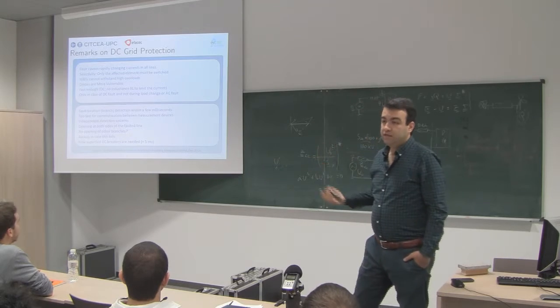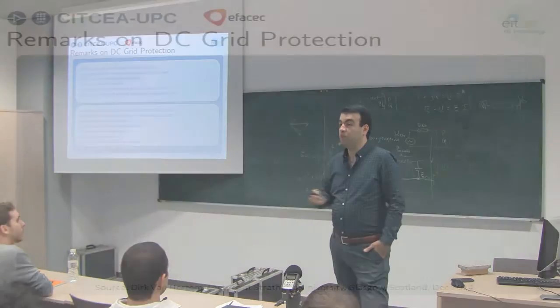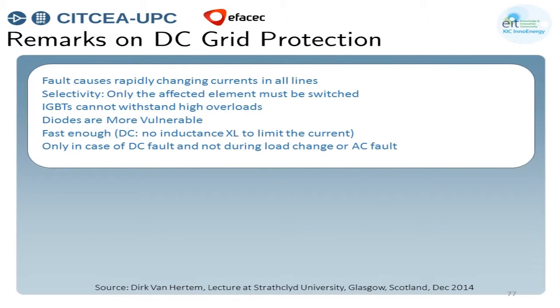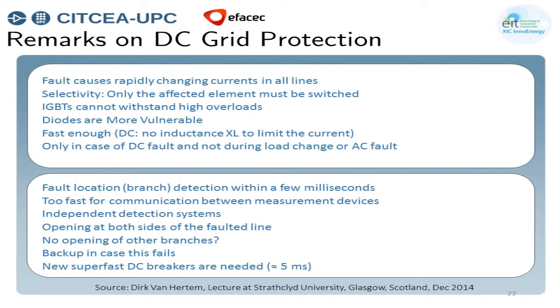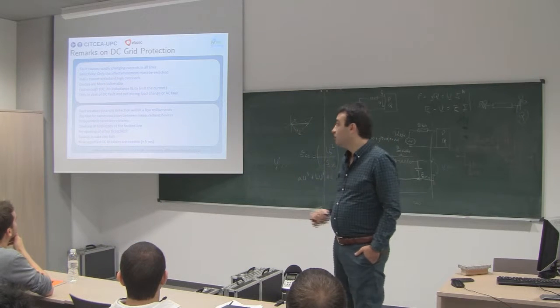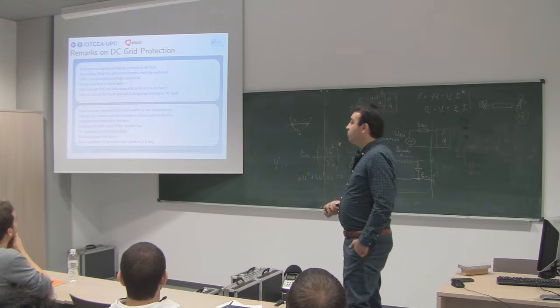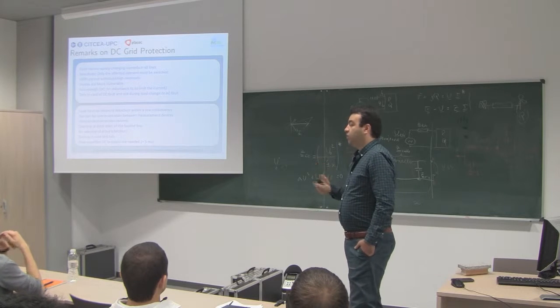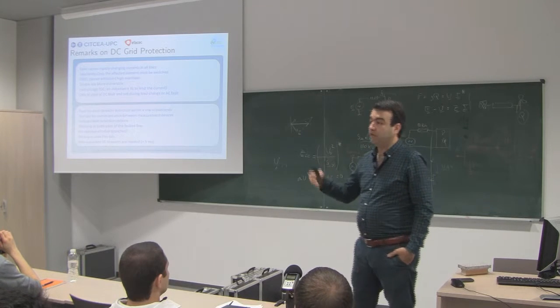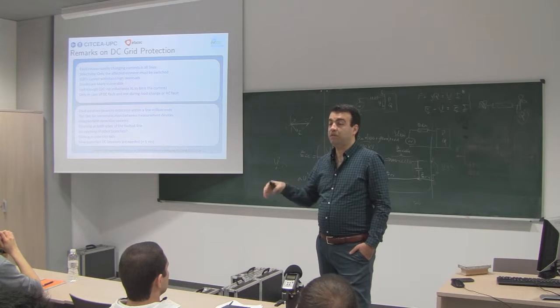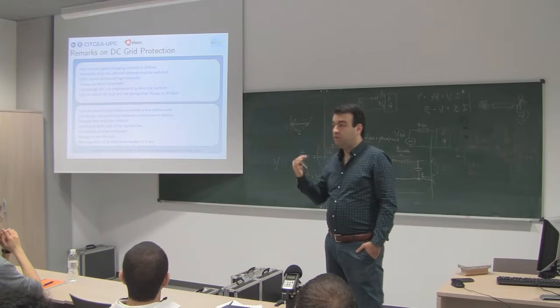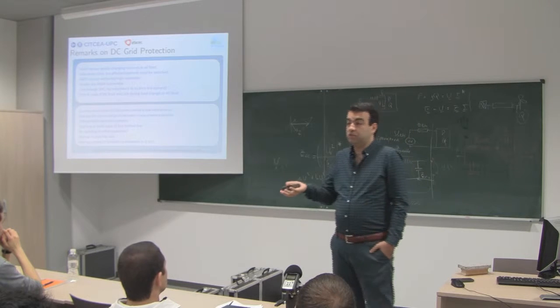Usually in the AC grid, our relays rely on some kind of communication between them to decide which line is really the faulty line. But in DC, it's not possible because the propagation of the fault current is much more rapid than the communication, or we can say it has the same velocity. So selectivity will be a problem. You will also have some fault identification problems depending on the topology of the grid. But the main challenge will be how to interrupt this current.